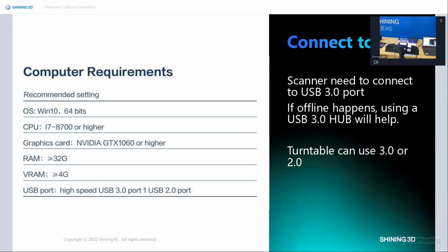And we do see some of the offline issues happen. We just updated the software to the 1.4.0.2.1 version, and this version gives you a firmware update which is supposed to solve most of the offline cases. However, we do see one case where even with the newest firmware, the scanner still has the offline issue. This is probably because the computer USB port is not good enough. Some computer USB ports don't have good power support. So a way to do it is using a USB 3.0 hub to connect through to your computer. I would say this is kind of an ultimate solution. It will definitely solve the problem if you have an offline issue.